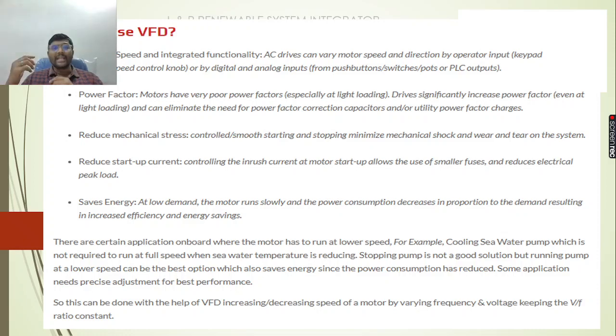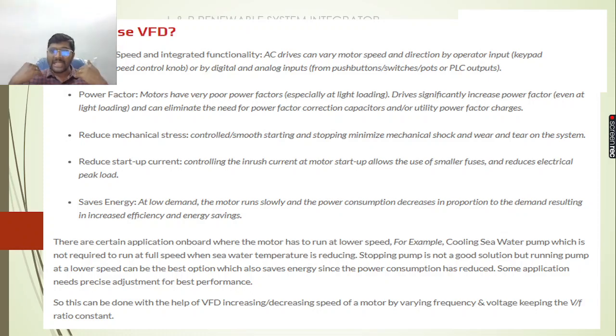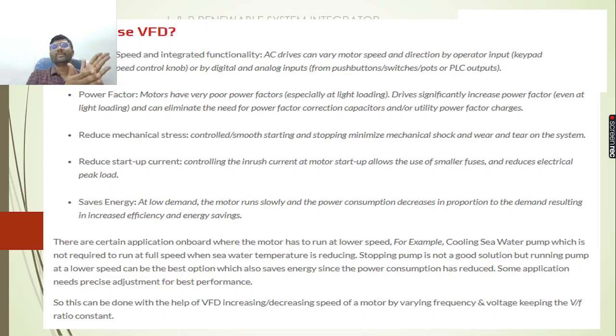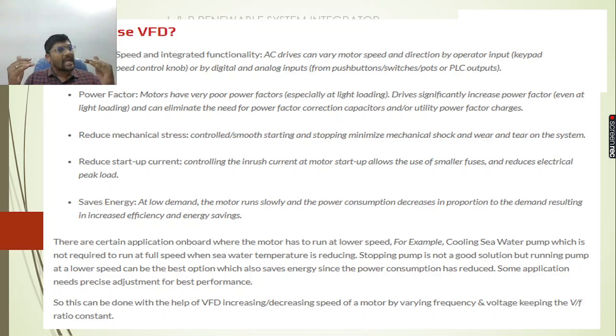Next, we can also reduce the mechanical stresses. Apart from VFDs, if you are using gearboxes for speed control of motors, this VFD is a better alternative. Most importantly, when we connect our motors directly with line voltages, what happens during starting time is the startup current will be high, and since it has more windings, the current will be maximum — creating a possibility for the windings to get damaged. In order to reduce this, with the help of variable frequency drives we can reduce the startup current. We can also save energy, since power consumption decreases when we use variable frequency drives. Based on demand, we can increase the speed; if there is no demand, we can reduce the speed and run the motor at a constant speed.